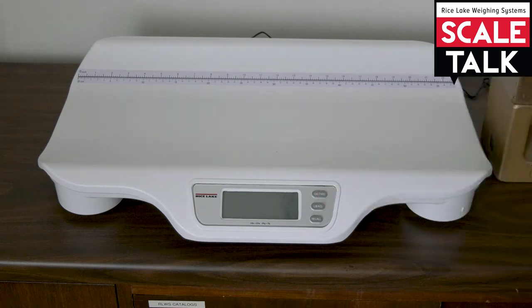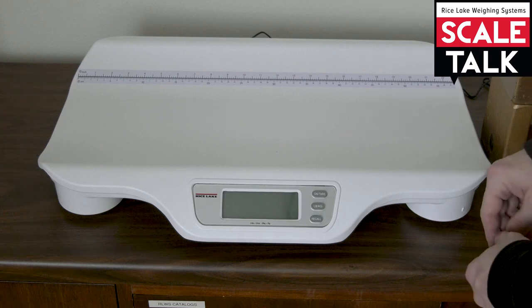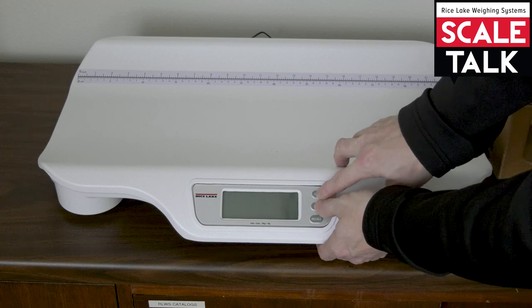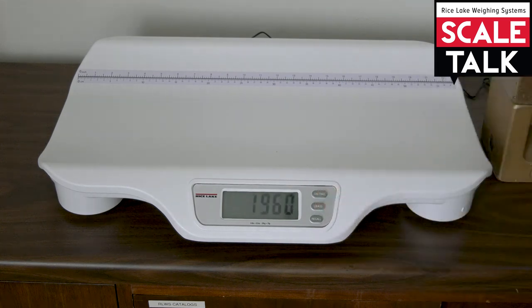Press on-tare to turn the unit off at this time, because when we go through calibration we have to start with the unit powered off. Now, to get into calibration mode, we're going to press and hold the on-tare and pound kilogram keys until we see raw counts on the display. There they are. At this point I can go ahead and press the on-tare key.